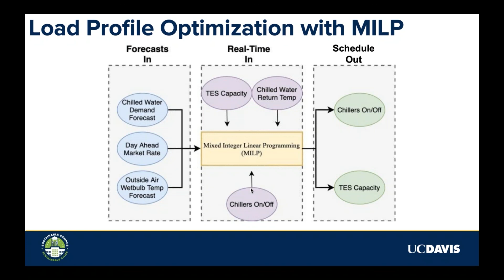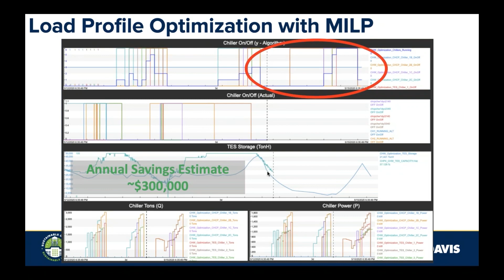So this top graph shows you what the optimization recommends. After this dashed line, that's the future, the next day ahead, and it says when to turn on a particular chiller. And then you can see the optimization compared to what actually happened. And then you can see the prediction of what the thermal energy storage tank capacity should be compared to what it actually was. And so using this program, our estimate is that we could save $300,000 a year.